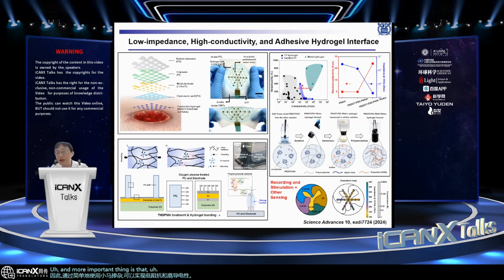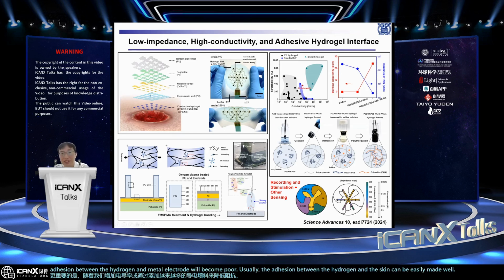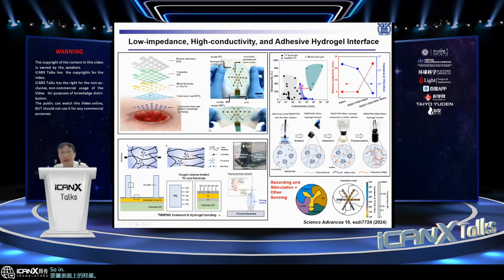And the more important thing is that as we increase the conductivity, or as we decrease the impedance by adding more and more conducting filler, adhesion between the hydrogel and metal electrode will become poor. Usually, the adhesion between the hydrogel and the skin can be easily made well, but we also need good adhesion between the conducting hydrogel and the metal electrode layer. And in this case, to increase the adhesion property between the hydrogel interface and the metal electrode, we functionalize the surface with hydroxyl groups and use a chemical, TMSPMA, to make covalent bonding between the polyacrylamide layer and the hydroxyl groups on the device surface. So in such a case, the conductive hydrogel interface could make very good adhesion to the electrode.